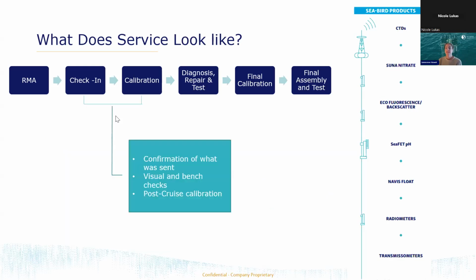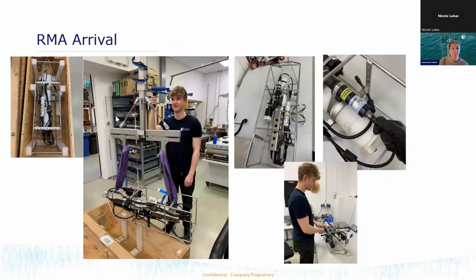And the next step in the process is really where we kick off our evaluation. So we have 2 steps. One is called check-in, where we're taking a look at what's arrived. I'll go through that in a second. And then we actually have a calibration step. We frequently refer to it as a post-cruise calibration. So the instruments have been out, they've been on a cruise, they've been used, and now they're coming back. But this is actually a critical diagnostic step for us, and it can be really valuable for data correction because sensors drift over time, and that drift is correctable. So it's an important measurement and diagnostic step for us.